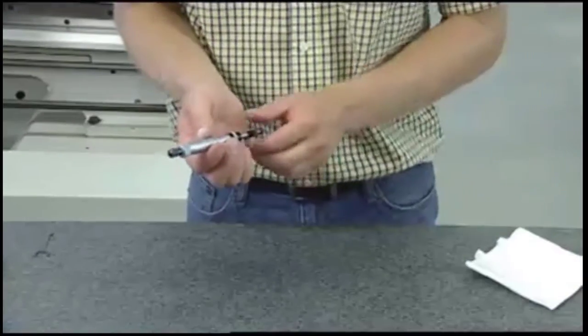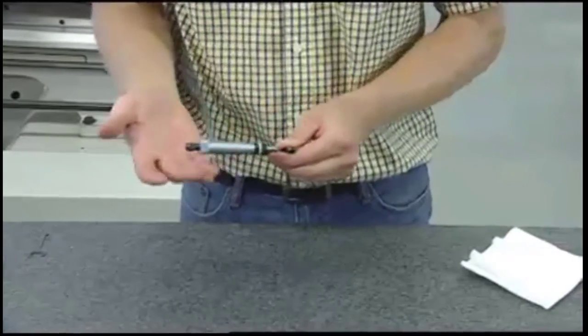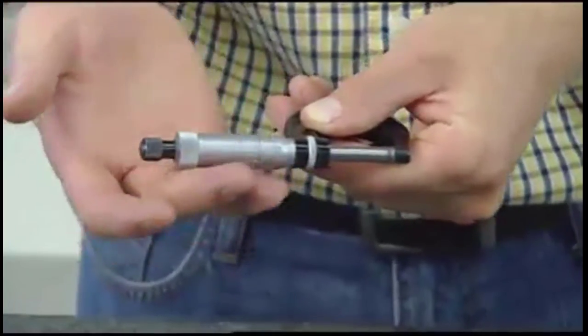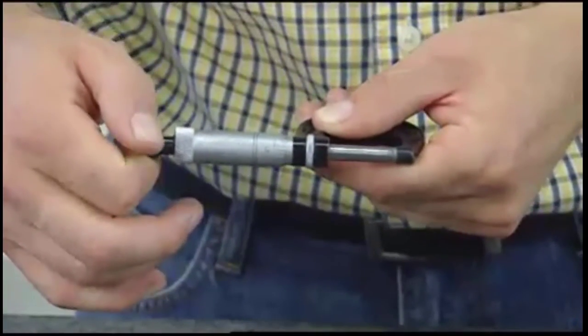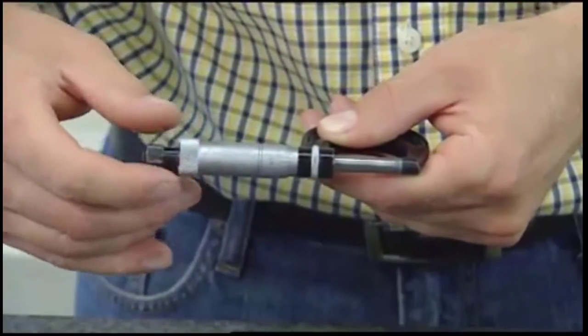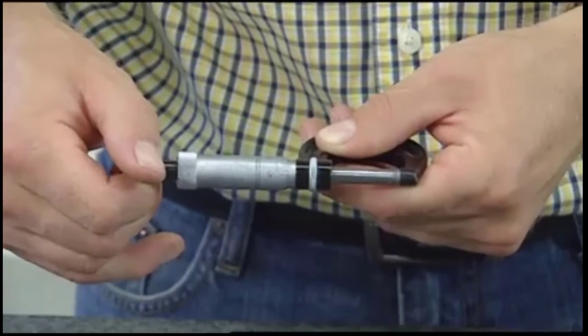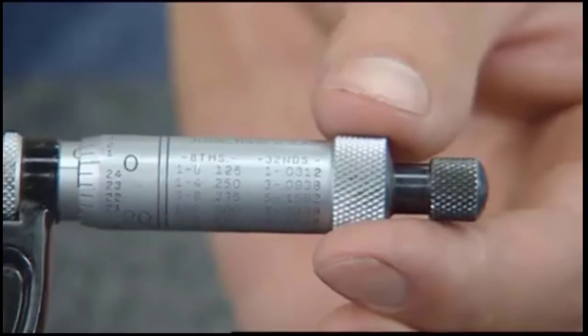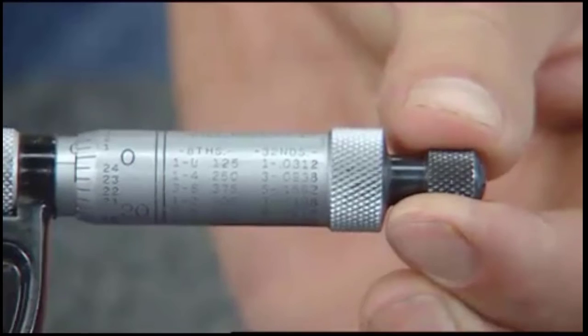Then close the micrometer spindle under the same amount of pressure as you would to inspect a dimension. Check to see if the micrometer is zeroed by examining the graduations on the thimble and sleeve. If the zero marks are not aligned, you will need to make an adjustment.